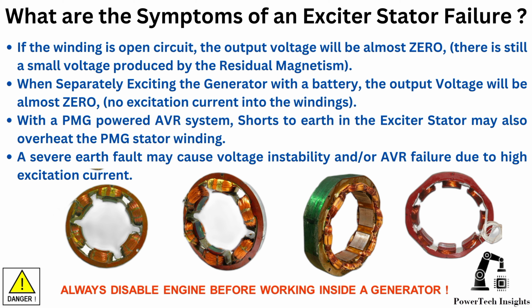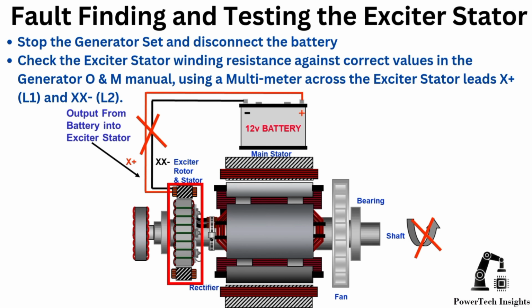When separately exciting the generator with a battery, the output voltage will be almost zero, with no excitation current into the windings. With a PMG-powered AVR system, shorts to earth in the exciter stator may also overheat the PMG stator winding. A severe earth fault may cause voltage instability and/or AVR failure due to high excitation current. Fault finding and testing the exciter stator. Stop the generator set and disconnect the battery.